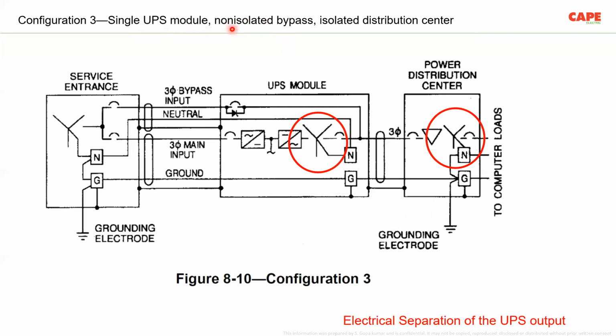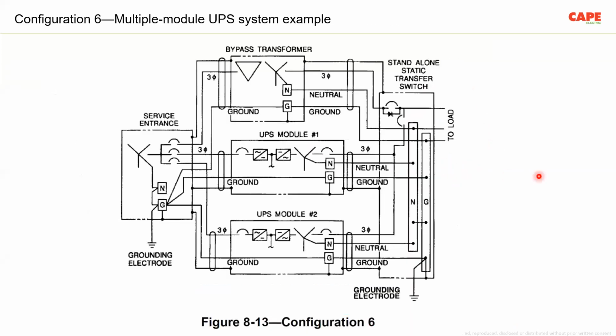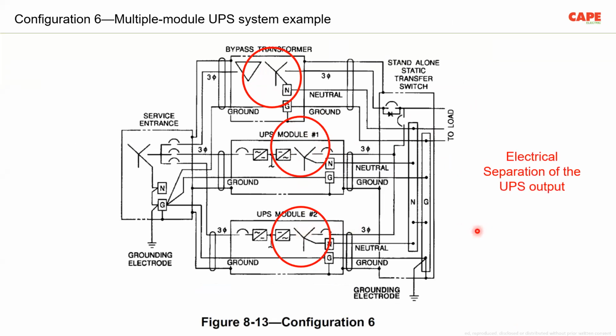This is a single UPS module, non-isolated bypass, isolated distribution center. In this particular case, you see the neutral, which is coming either from the input side or from the star point, is terminated there. It is not extended to the load. So at the output, you have another distribution transformer, an isolation transformer. The neutral is connected to the ground terminal, the earth terminal, and it is earthed. So this is one of the configurations. Here is another configuration with a bypass, but of module type UPS. You can see UPS module 1, UPS module 2. Everywhere there is electrical separation. And most important, at this point, the neutral of this UPS is earthed. The neutral is connected to the earth bus bar.